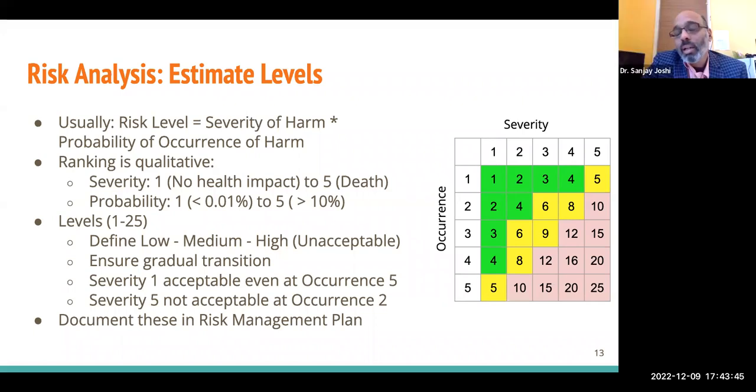I would say absolutely, because before they approve your device, again, stop me if I don't answer your question, okay, Pranita. So the first part of the question: there are different classifications of the device, right? The ABCDs, and like in India, EU has class 1, then 2A, 2B, 3. US has the same thing, class 1, 2, 3. The classification of the device, as Pranita said, is a completely different game, right? The risk analysis is, no matter what your classification is, you still have to do risk analysis. Again, what changes is the severity and occurrence based on the classification of your device.